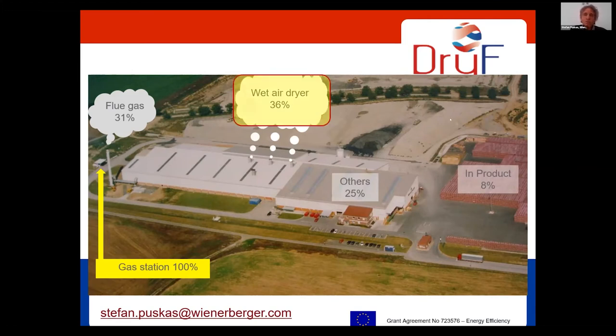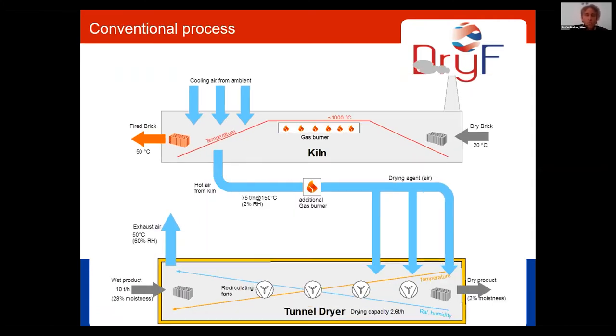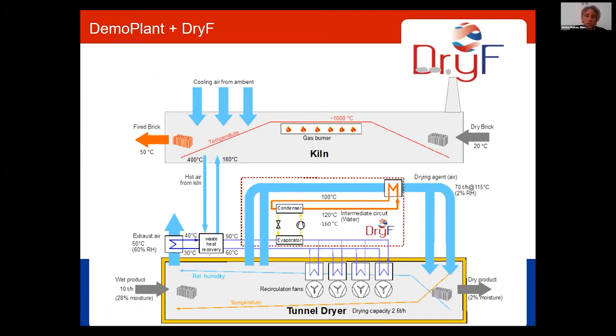So we have to focus on this energy source. Our losses are by far higher than mentioned in the introduction, what is average in the industry in Europe. So we have this situation you've seen before, the kiln and the dryer and the losses through the exhaust air chimney from the dryer. Now we want to pick this energy, and we have decided to do it in a two-stage process. These projects are called demo plant and dry efficiency.